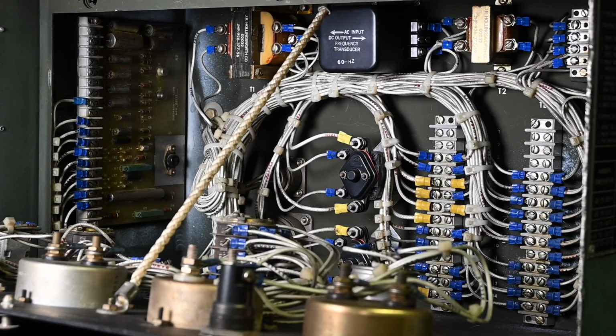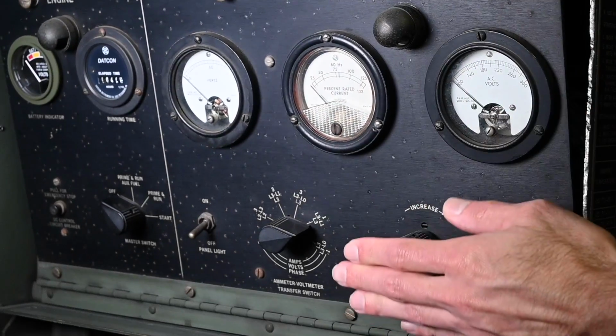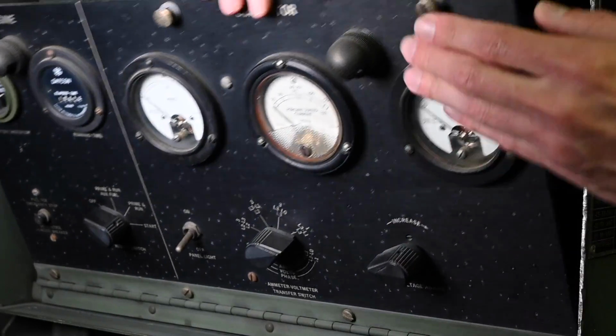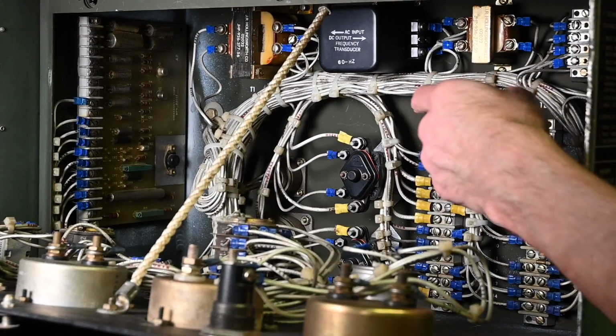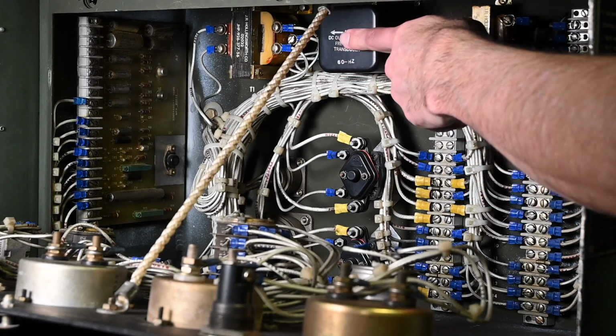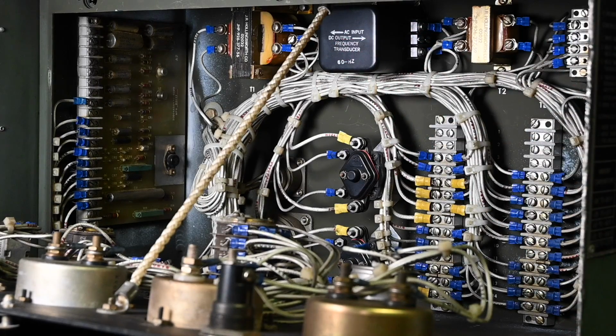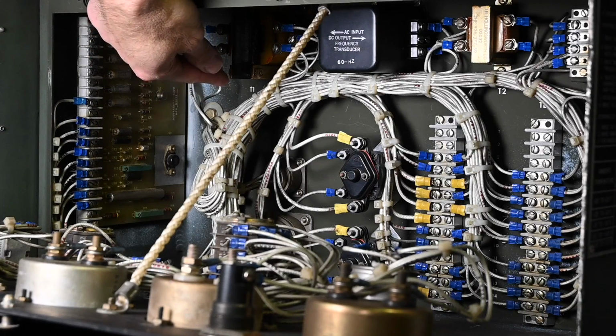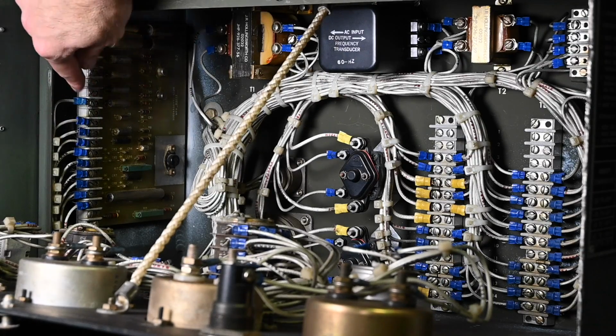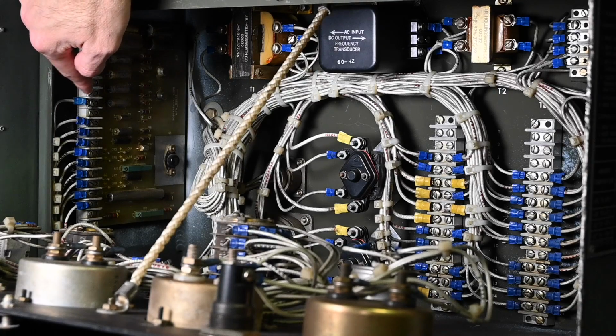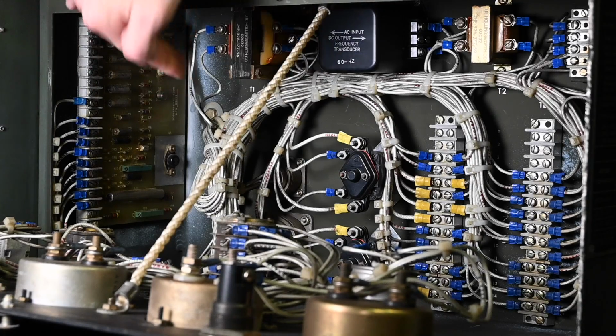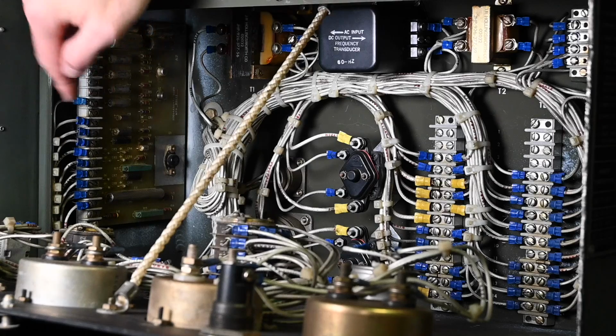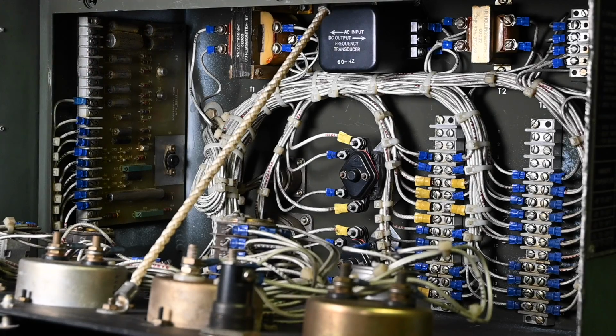All right, here we are looking inside the control panel. So this is the AC voltage adjust rheostat, which is marked as R1. This is transformer T2. This is a frequency transducer. It doesn't have anything to do with the voltage regulation. It just drives the front panel frequency meter. This is transformer T1, and that's assembly A2, and this is the voltage regulation circuit board. Now these two transformers provide voltage to that circuit board. There are more components related to the voltage regulation down in the AC reconnection box, so let's take a look.